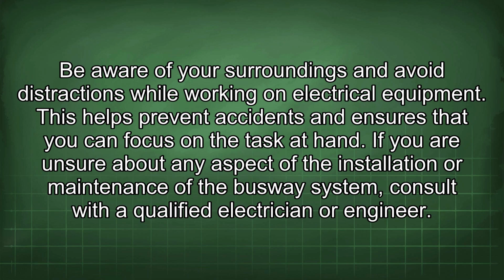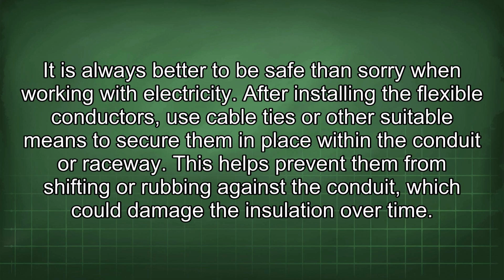If you are unsure about any aspect of the installation or maintenance of the busway system, consult with a qualified electrician or engineer. It is always better to be safe than sorry when working with electricity. After installing the flexible conductors, use cable ties or other suitable means to secure them in place within the conduit or raceway. This helps prevent them from shifting or rubbing against the conduit, which could damage the insulation over time.